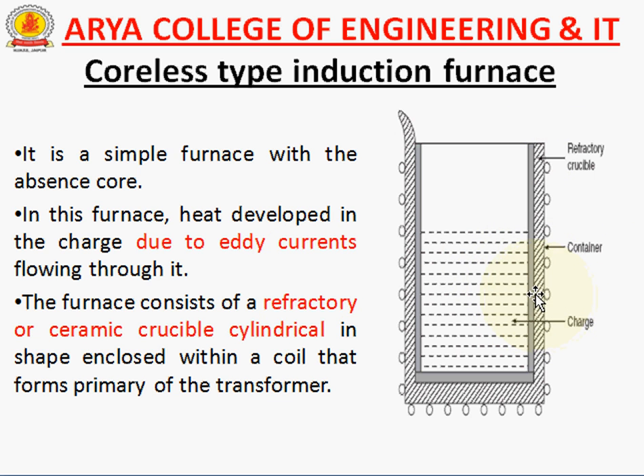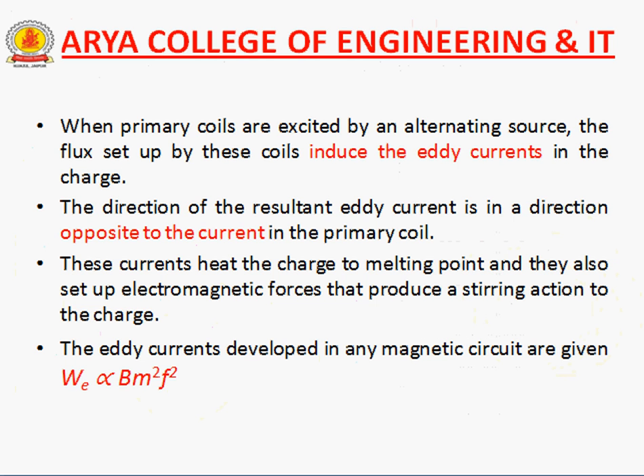The heat becomes produced due to the eddy current. When the primary coil is excited by an alternating source, the flux set up by this coil induces eddy currents in the charge. The direction of the resultant eddy current is opposite to the current in the primary coil. This current heats the charge to the melting point and also sets up electromagnetic forces that produce a stirring action in the charge. The eddy current loss is proportional to Bm² × f².